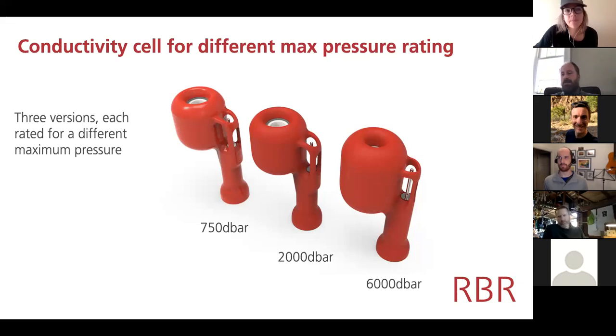Some people have had success putting copper mesh around the guard, for instance, in very active areas. And those are areas where typically you're not looking at very small signal in any case. So it's a bit like this question about the proximity effect. Your sensitivity to it is less. One thing to note is the correction for putting in place any kind of object in proximity, in salinity, is purely an offset. If you've got a bucket of water that's well stirred and you measure salinity, and then you attach your very, very close metallic frame to the instrument and you measure salinity again, you'll get a difference between the two. You can use that as an offset across the entire measurement. So in salinity, it's an adder or a subtractor. In conductivity, it's a multiplier.